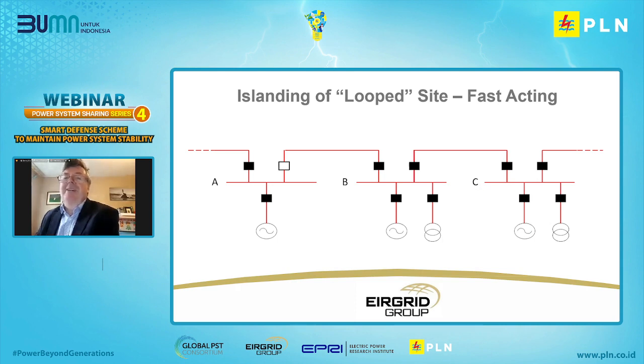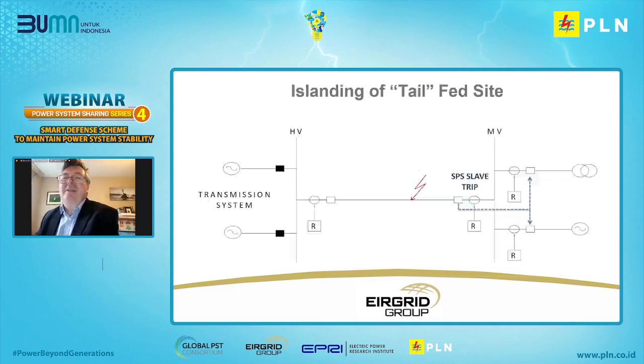Sorry, can you go back one slide? Go back one more. Yeah, so here, the fault on the tail feeder has islanded generation here. And so then the open breaker status is used to open the breaker on the generator and on the load. So basically opening all breakers and shutting down the island. Okay, we'll move on to the next slide.